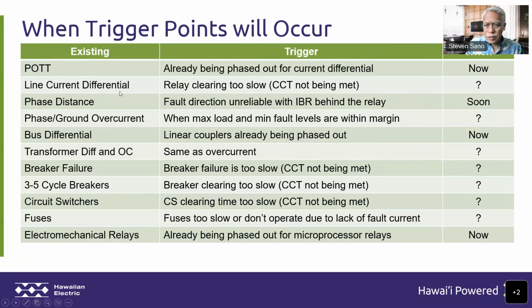Changing line current differential to traveling wave. We haven't seen anything on our system that would indicate we need to change that. And again, it's a critical clearing time not being met by current differential schemes. Phase distance, fault direction unreliability. We see some of that already, so there are changes being made. Phase ground overcurrent, when max load and min fault levels are getting too close to each other.